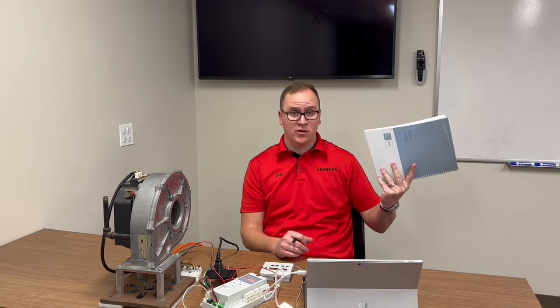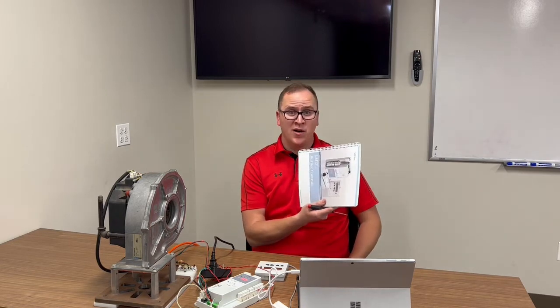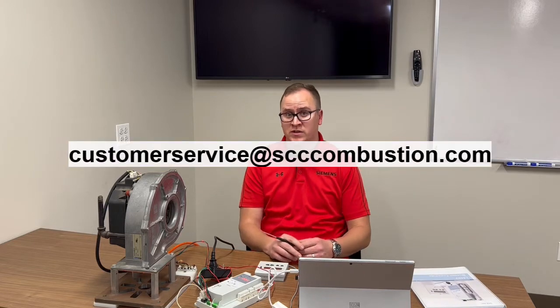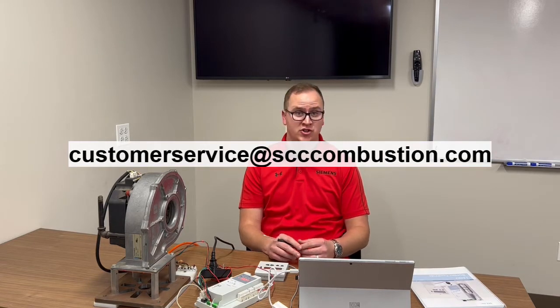Lock 83 and lock 225 are common speed faults. For help troubleshooting that speed fault, I recommend having the LME7 technical instructions. We have the spiral bound version here and also the electronic version in PDF. If you'd like the spiral bound version, I recommend sending an email to customerservice at scccombustion.com.